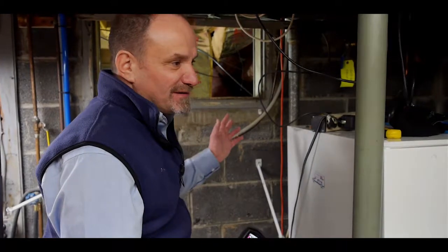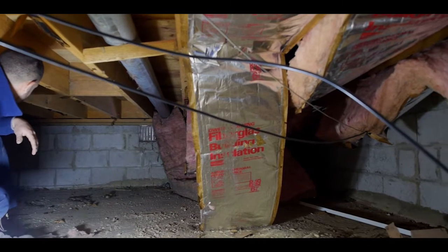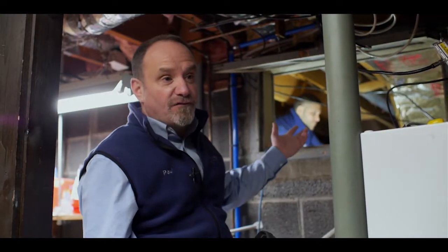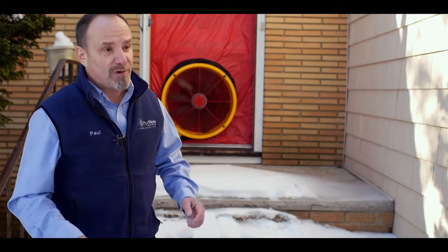So now we're getting somewhere. We've found some other smaller problems, but this is a big one — a vented crawl space to the outside, below that kitchen area. This is what's going to kill the floor surface temperatures upstairs. There's insulation inside here that's all falling down. It's vented to the outside and it's going to make that kitchen floor feel like it's the outside. I think we found all the problems. The guys are going to spend some time here today, seal up all the problems, and we're going to come back later and see how they did.